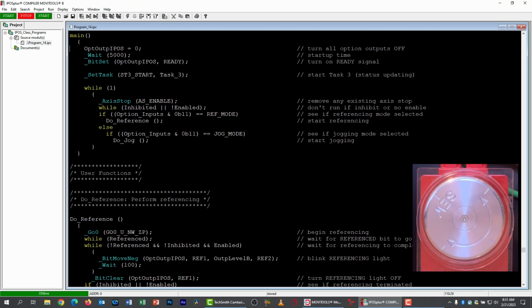Now let's look at something here. I'm going to turn DI11 back on again, and I'm going to change direction. Watch the drive. Notice it doesn't change direction right away. That is because it's trying to complete the positioning operation that you've sent it, and they actually start building up. So what's going to happen is it may take a number of turns before it finally catches up and it changes direction.